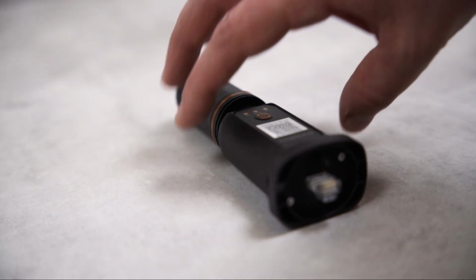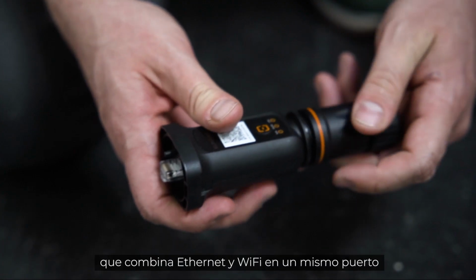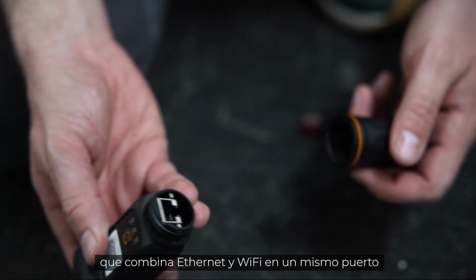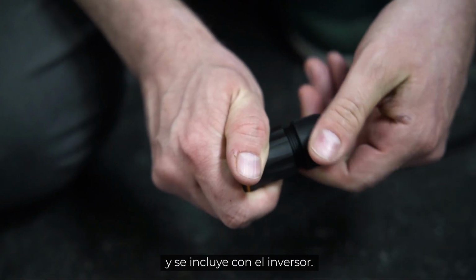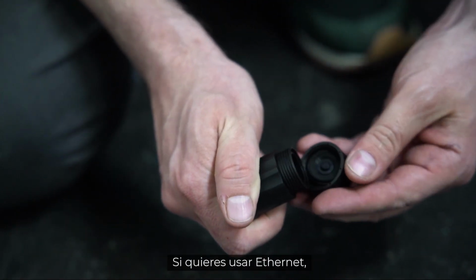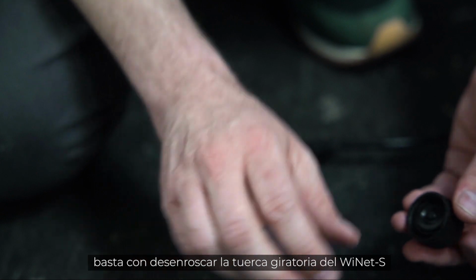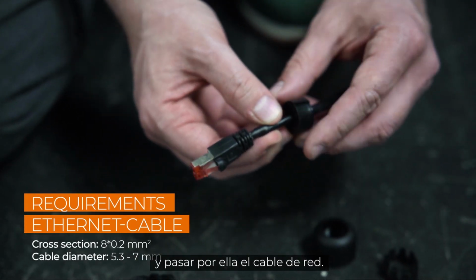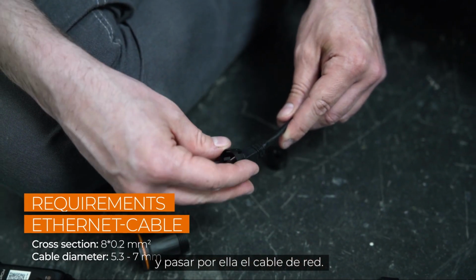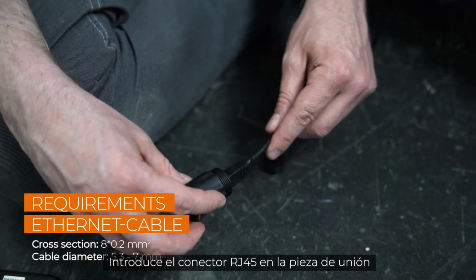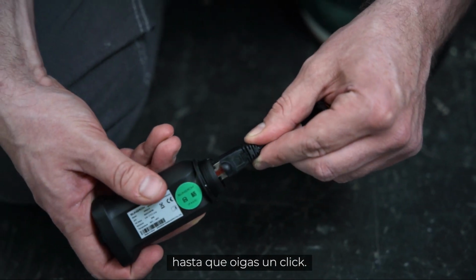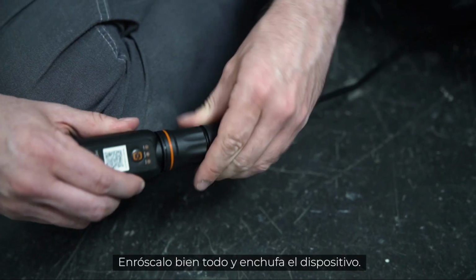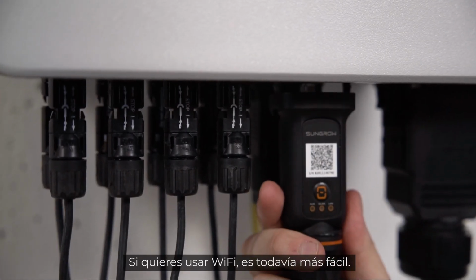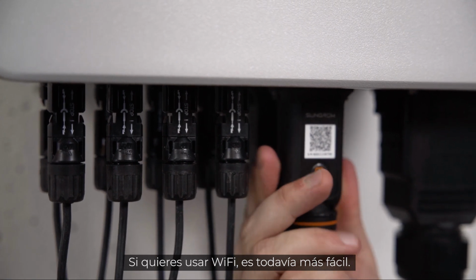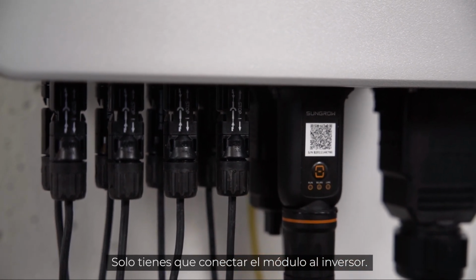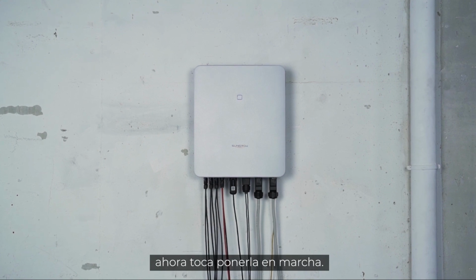For commissioning, you have to connect the new WiNet module. It combines Ethernet and Wi-Fi in one port and is part of the delivery scope. If you want to use Ethernet, simply unscrew the swivel nut from the WiNet-S and thread the network cable through it. Insert the RJ45 plug into the plug connector until you hear a click. Screw everything together and plug the device in. If you want to use Wi-Fi, it's even easier. Simply connect the module to the inverter. That's it. The installation is done.